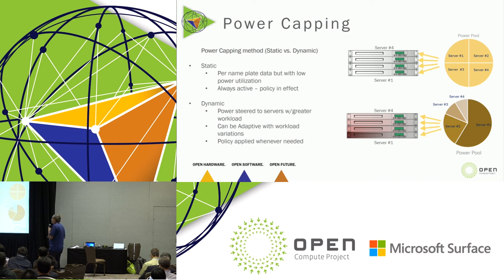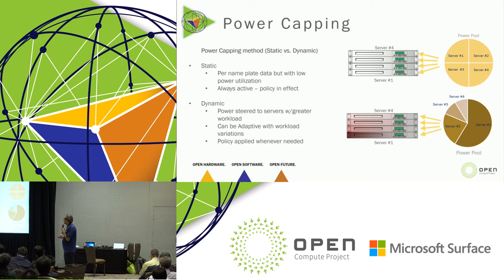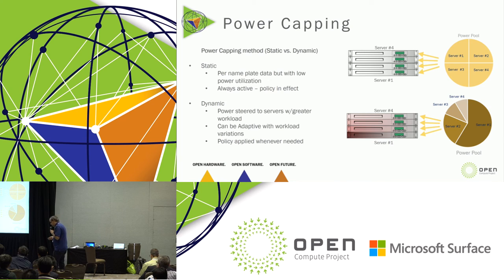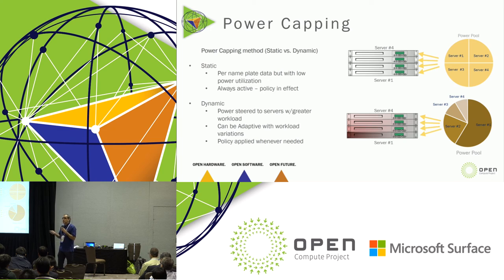The second approach — dynamic power capping — is more efficient at directing power to workloads that need it. We still have the same power budget from the power pool, but we can allocate power based on the need of each workload, as this pie chart shows. The other benefit of dynamic power capping is that the policy is not always active — it's activated only when needed, versus static power capping which is always in effect. So if there is no power or cooling incident, servers can take full advantage of available power to deliver the best performance.